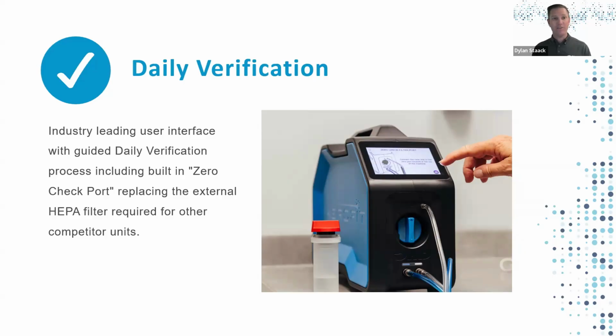Every time that your unit comes back for calibration, we get this question a lot. Every time your unit comes back for calibration, we're going to check that HEPA filter to make sure it's good. If it needs to be replaced, we're going to do a swap of that filter. You're never going to know that it happens. It's just something that we do with our checks and balances. Competing units require you to carry them around. A lot of times users will duct tape them to the side of the unit or something like that. With us, it's all internal.